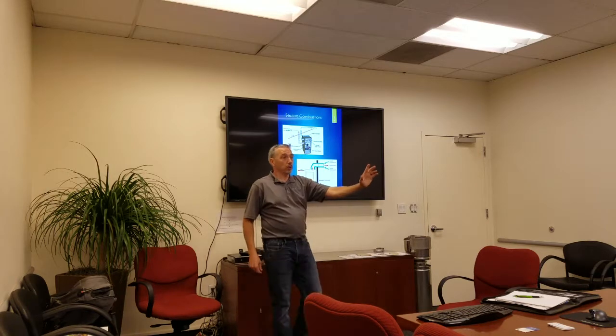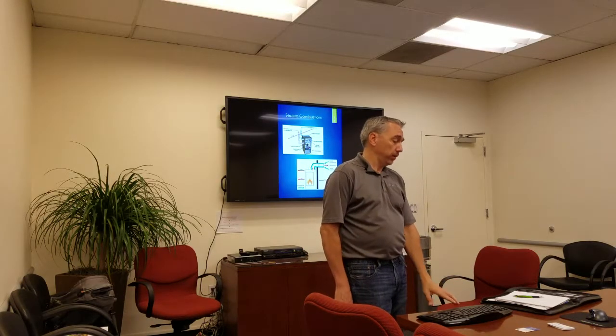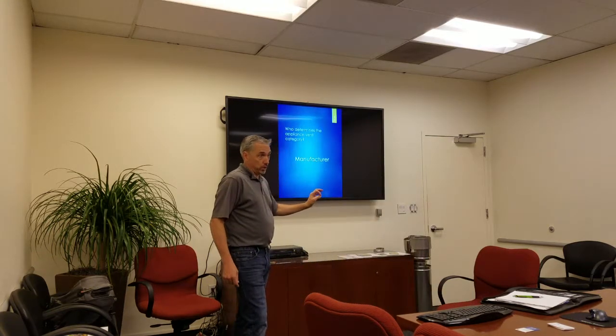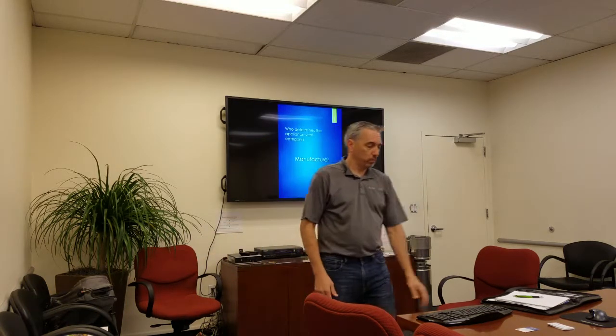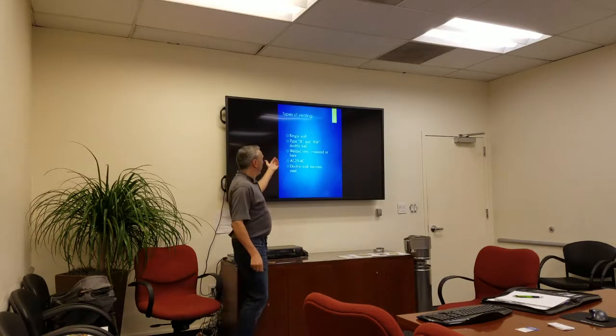We don't need vertical anymore — there's a blower in here that propels the flue products out, so vertical is no longer always needed. But who determines the appliance vent category? The appliance manufacturer. That's the only one who decides — it will be specified in their book and their literature, stating whether this is intended to be a category one, two, or four appliance.